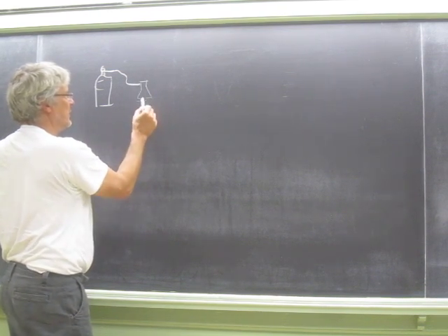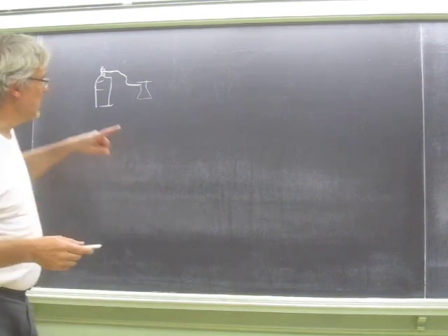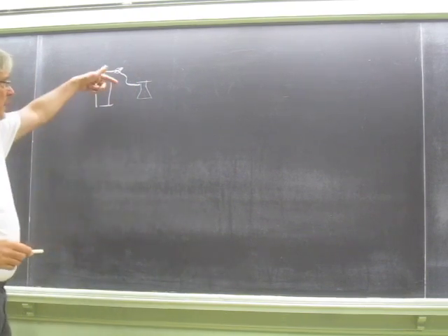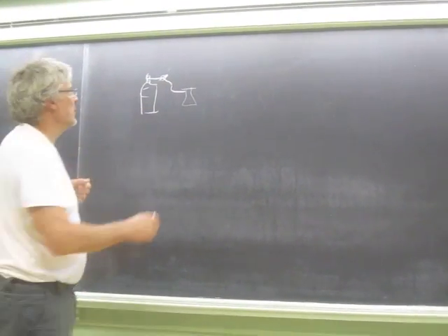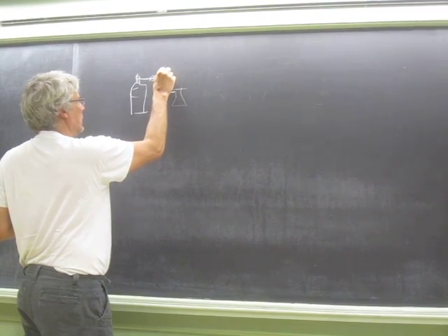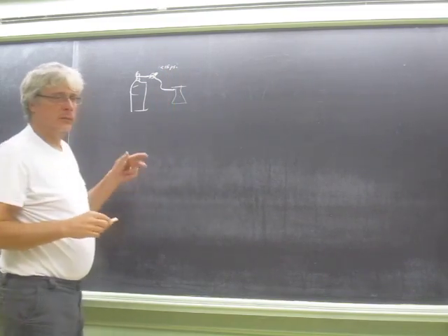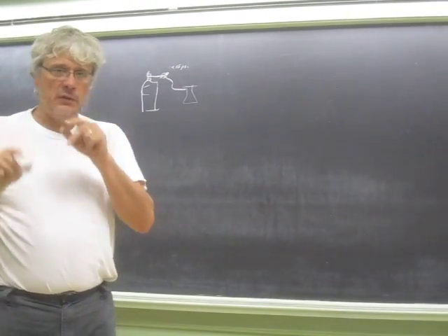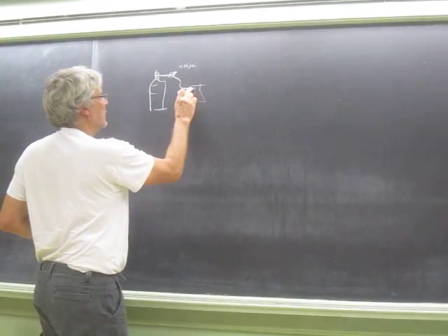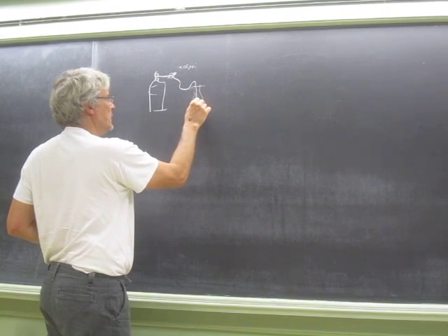And they look kind of complicated, and they probably don't need to be nearly that, but one of the things to realize is that since this is coming from a pressure regulator here, and that pressure regulator is set to a maximum of less than 15 psi. And the reason is that we don't want to have a safety issue of pressurizing the glassware and blowing it up. And so that gas actually comes in, and it just goes into a piece of tubing.